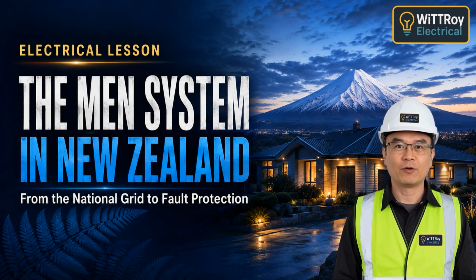Second, what is the main purpose of the earth electrode? Some students think the fault current normally travels through the earth electrode and the soil. Is that correct? Third, why do we need the MEN link? Why are the neutral bar and earth bar connected at the main switchboard? What does this connection actually do? John will answer these three questions throughout this lesson.